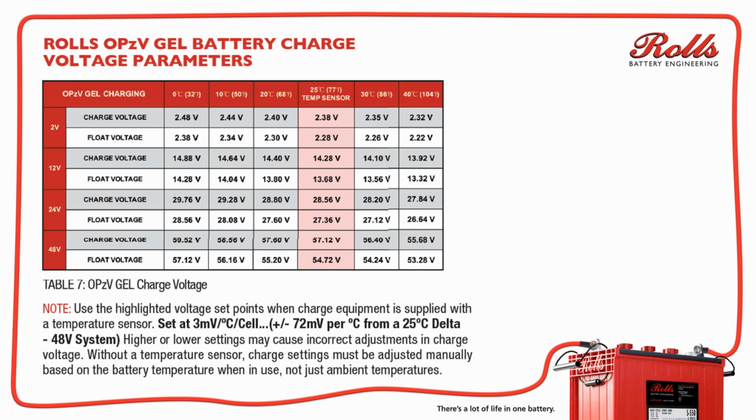And twice a year, you're going to see differences in settings. If you use the same winter settings for summertime, you're going to be overcharging your batteries and cooking them. And the same thing with summer settings in the wintertime: you're not going to be charging them well enough, because you get more power in the sun. So you've got to educate that client.